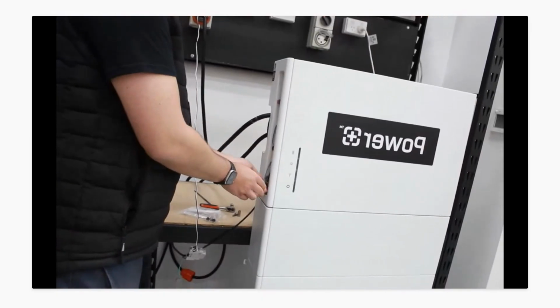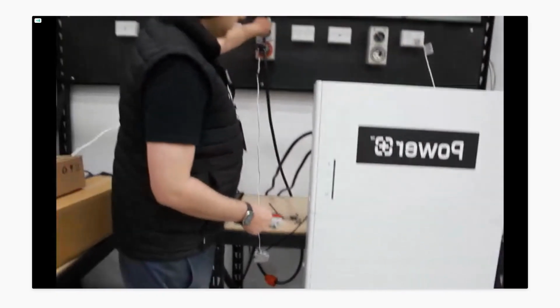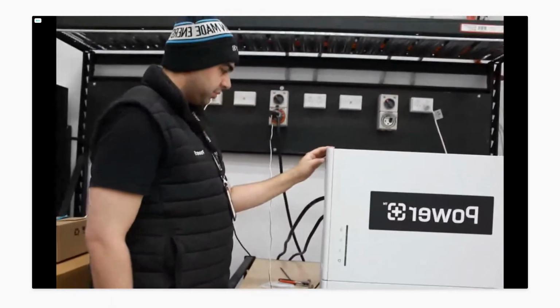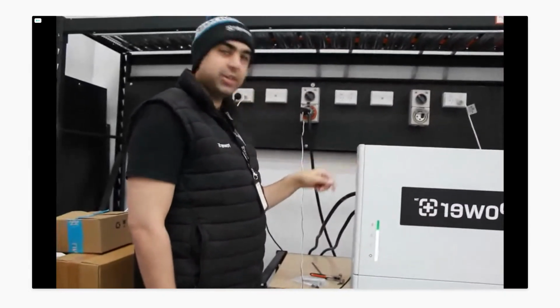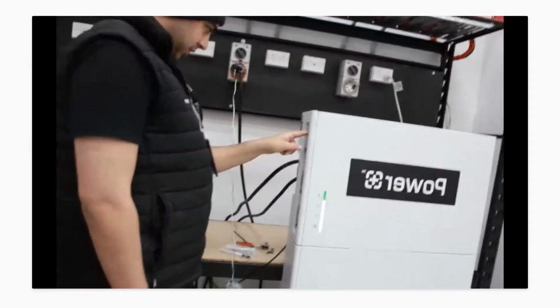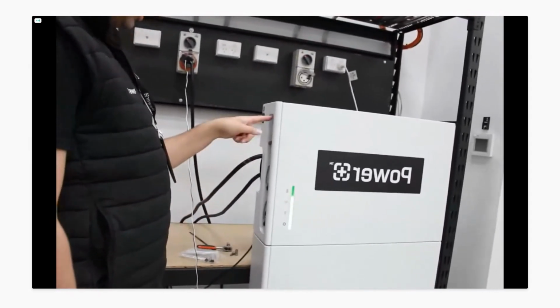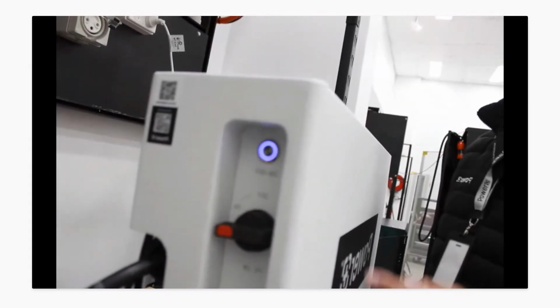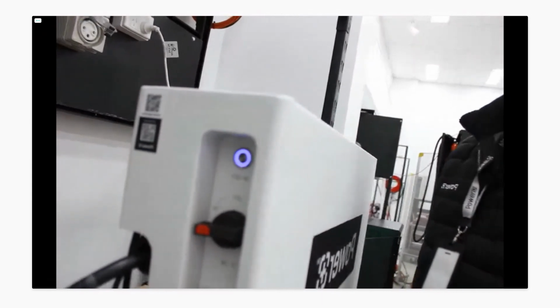So we've done our PV breakers, we've done our DC breakers, then we turn on our AC breakers. And now the grid will also help very much too. If the grid wasn't there, it would have turned on with the battery instead. So once I've got all my sources on, I can hit the on switch, which is now lit up blue. If you want to have a quick look, without the on switch depressed it won't light up. So if that's blue, then it's on.